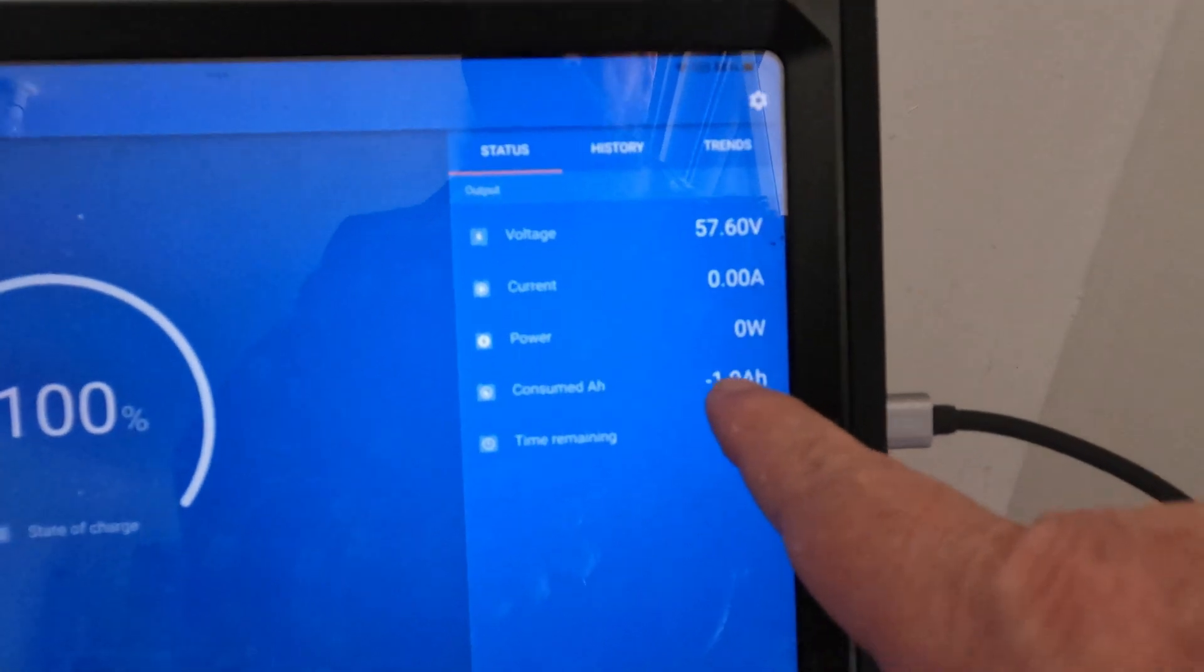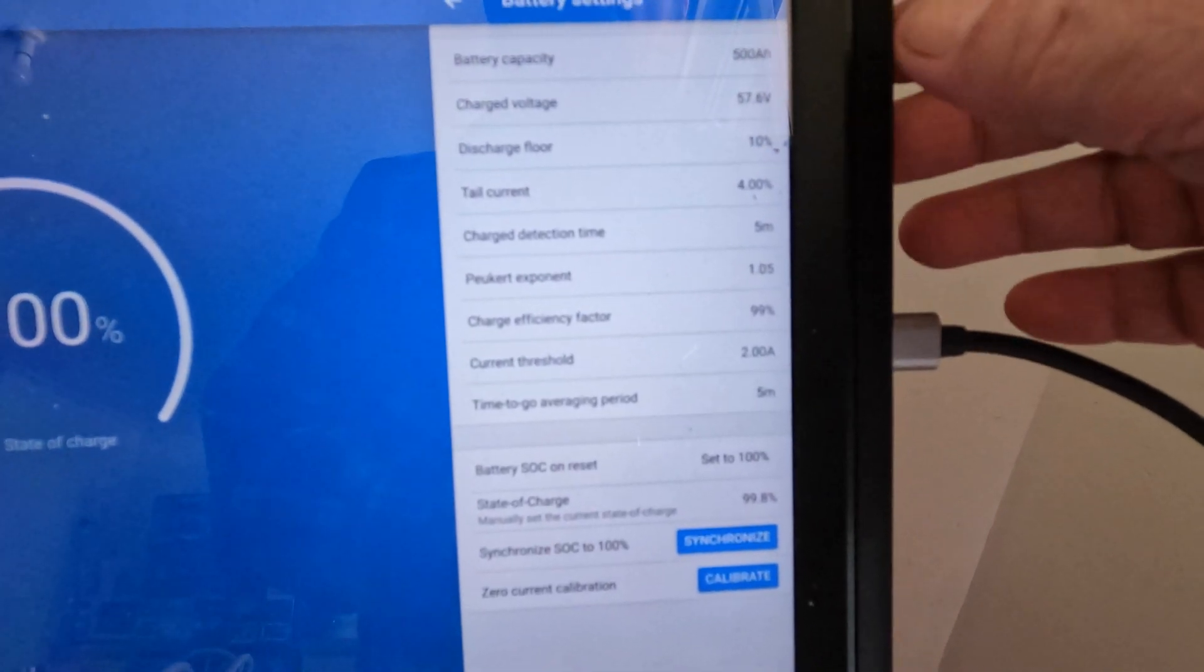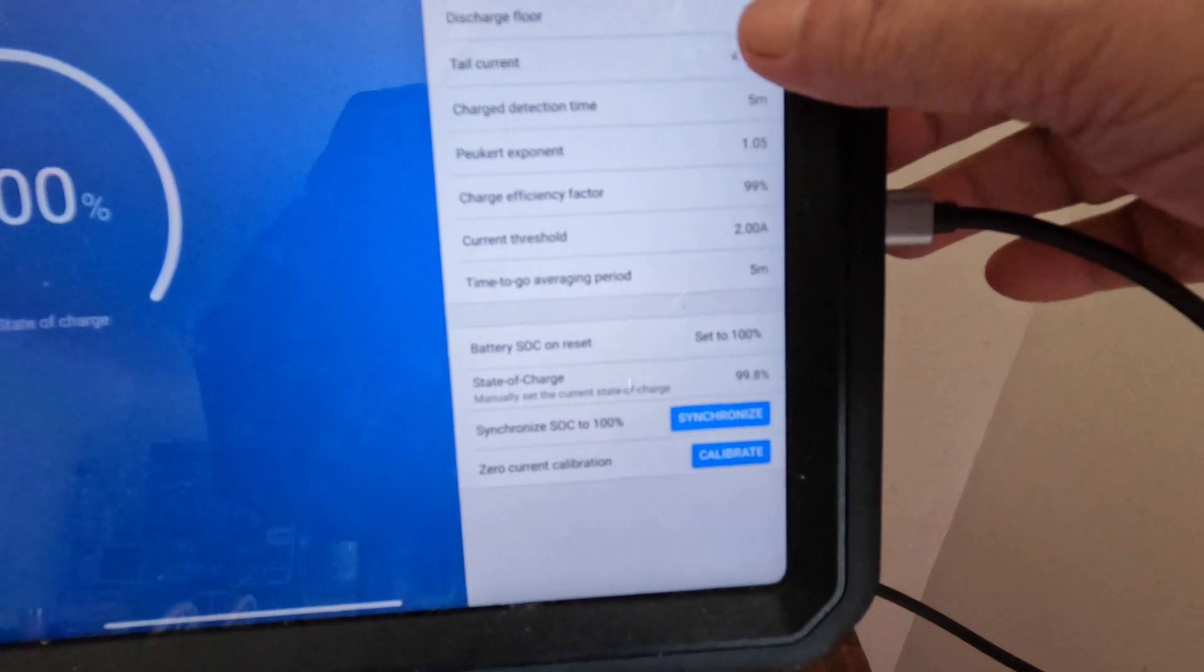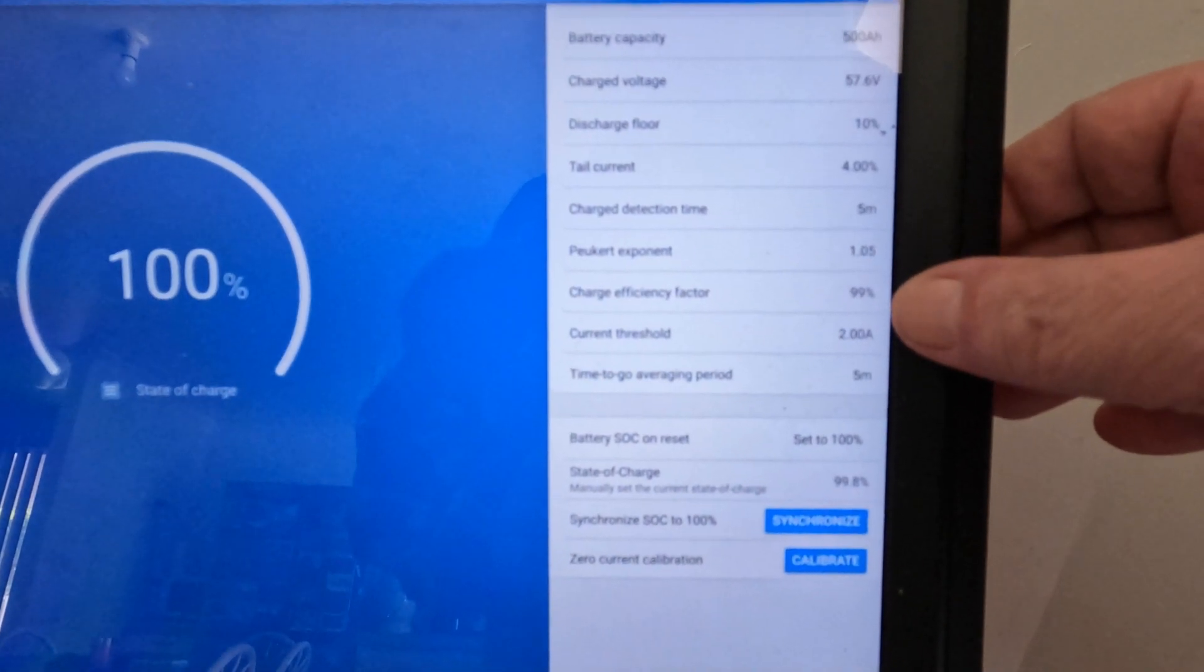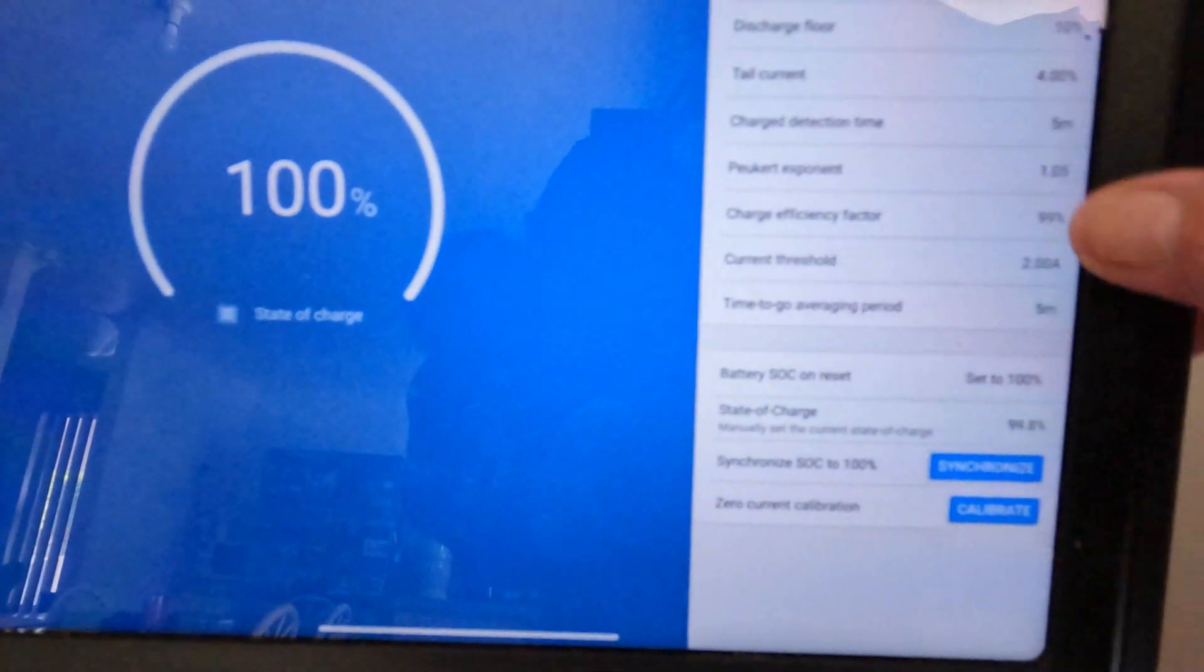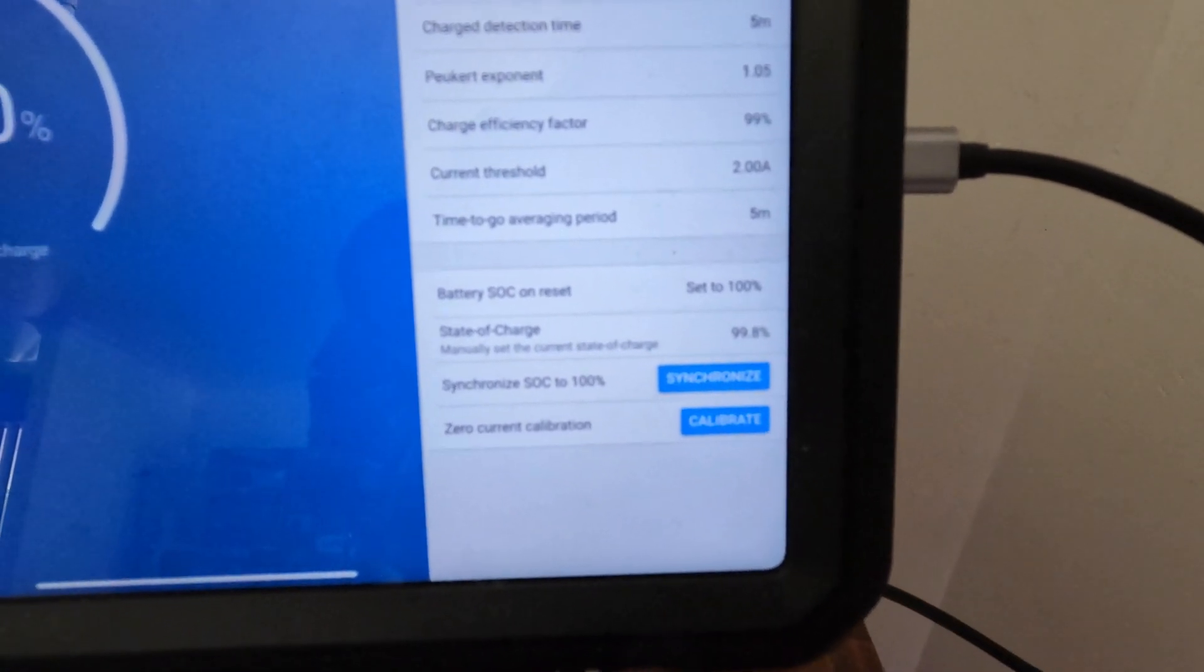The battery was chock-a-block full. This is the Victron I'm showing you. See this? I've got it set in the settings. I've got it set right, okay? 500 amp hour, 57.6 charge voltage. Tail current might be wrong because there is no tail current on these things, but anyway. The current threshold is probably wrong, but it said it's 100 percent full. But here it says it's 99.8 and it should be 100.